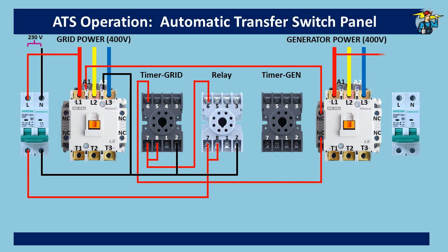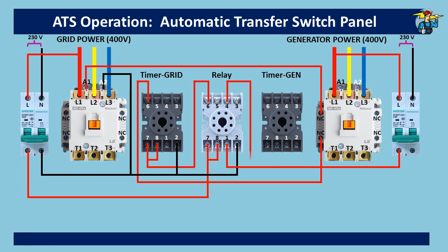On the generator side, we also take phase and neutral wires to the breaker first. The phase connection goes to the common port 1 of the relay. From the relay, the normally closed outlet port 4 takes power to the generator timer. Neutral wire is connected to timer port 2.